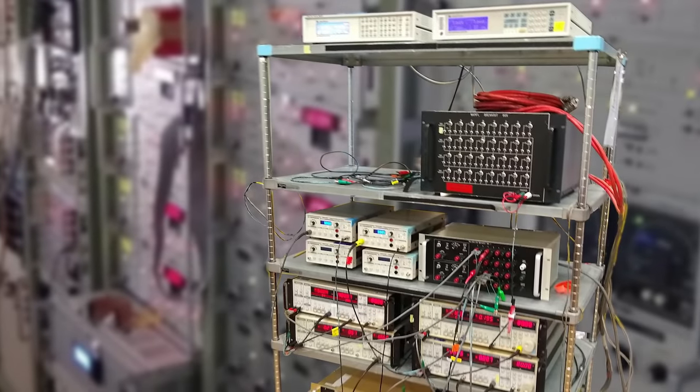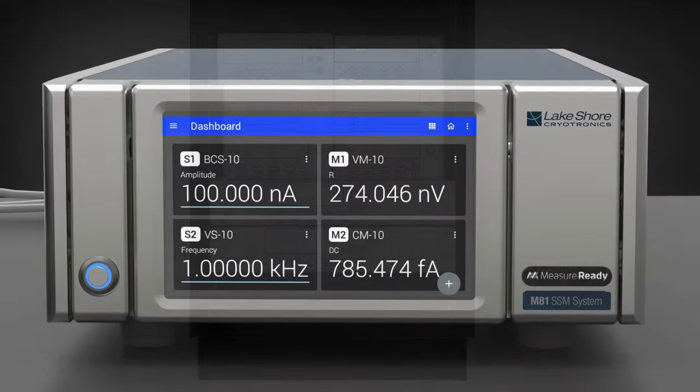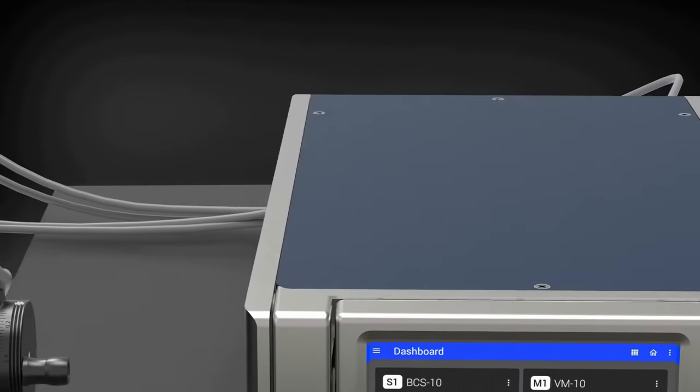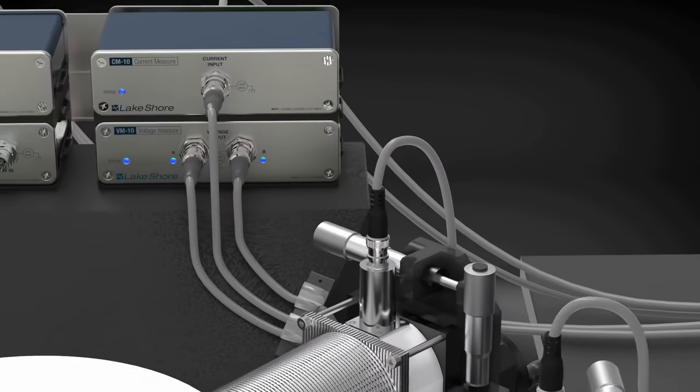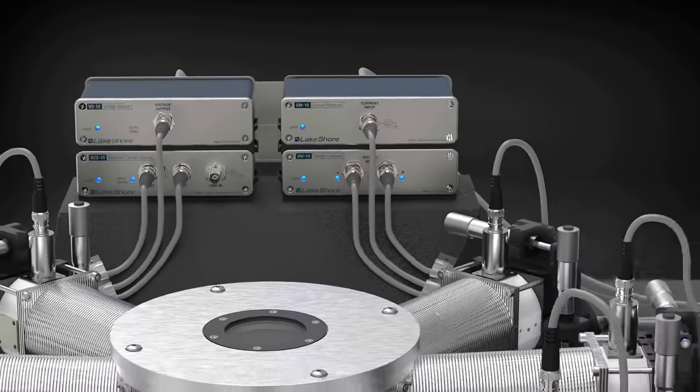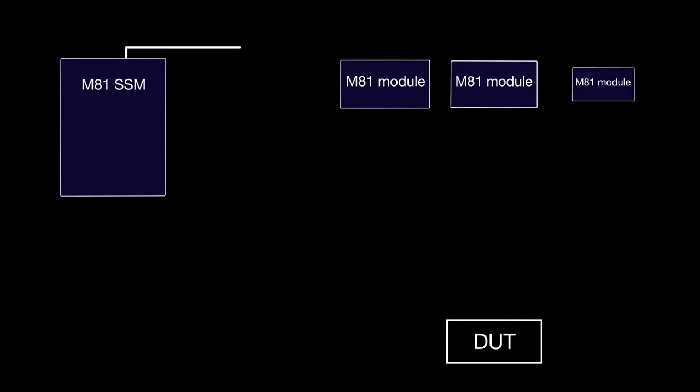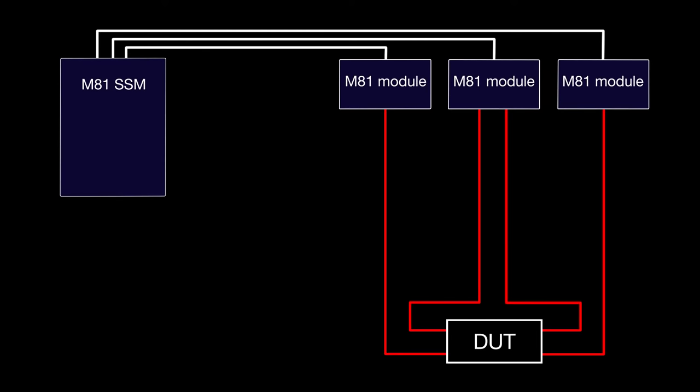Typical mixed-vendor instrumentation setups can be complex to operate and may also be compromising the quality of your measurements. The Model M81 SSM provides a unified, modular approach to multi-channel sourcing and measurement and allows up to six channels of source and measure amplifier modules to be remotely mounted from the instrument, providing flexibility and bringing the sourcing and measurement much closer to the sample or device under test.